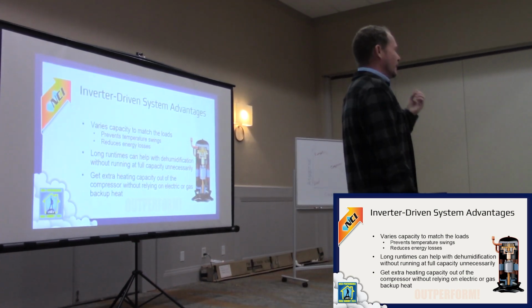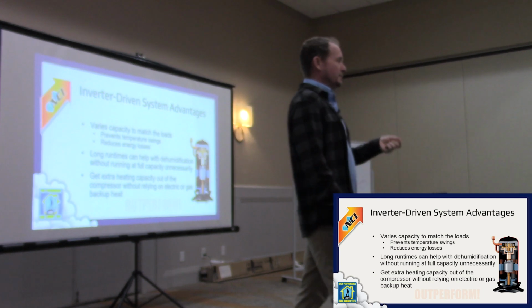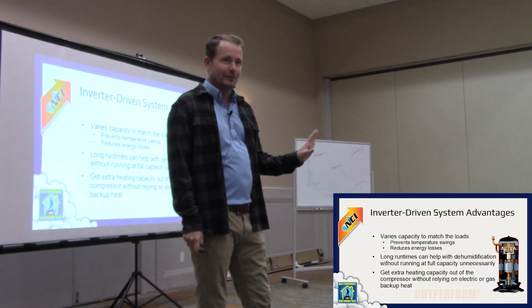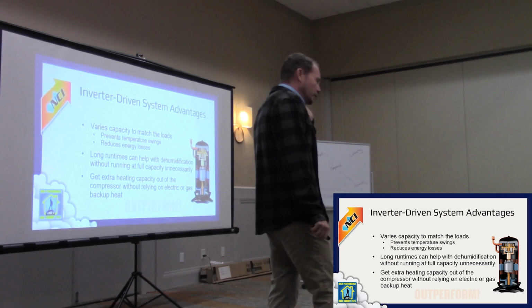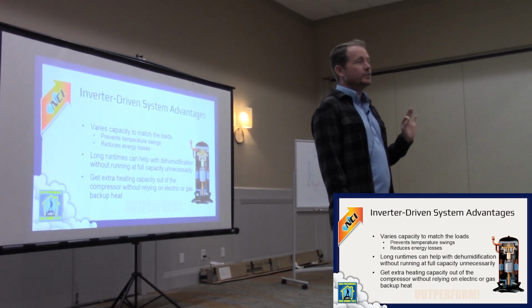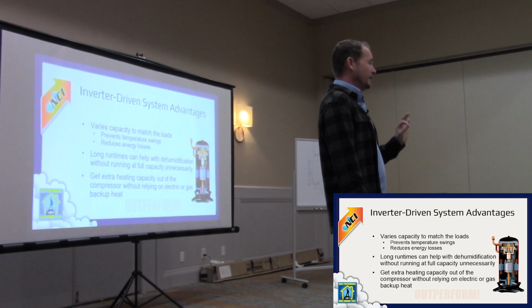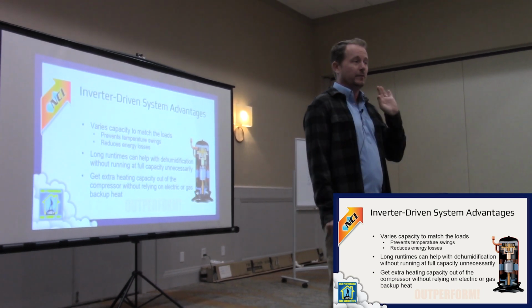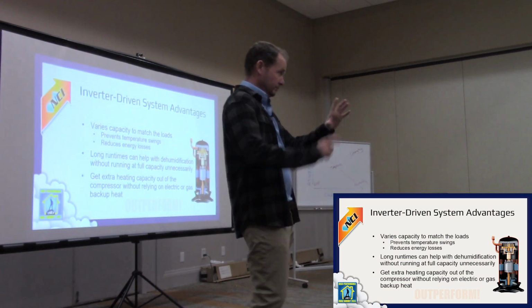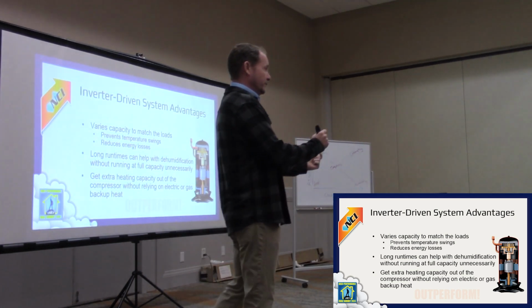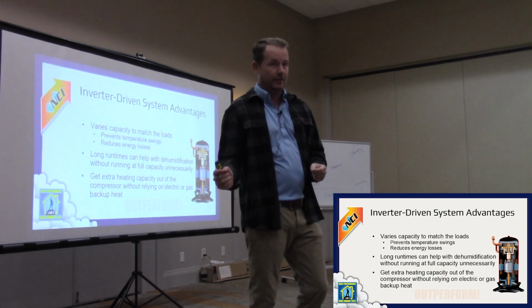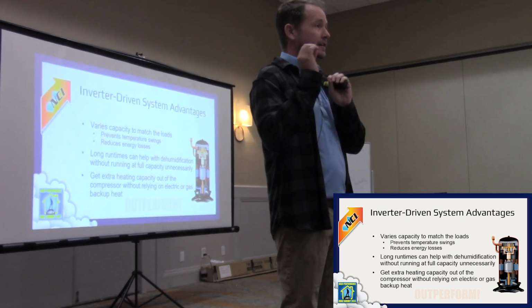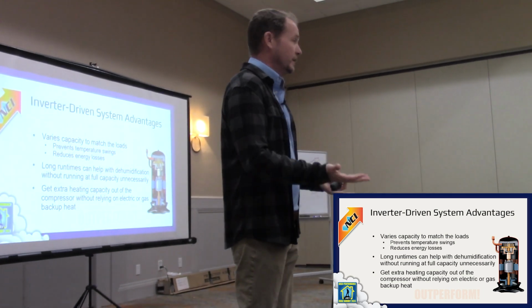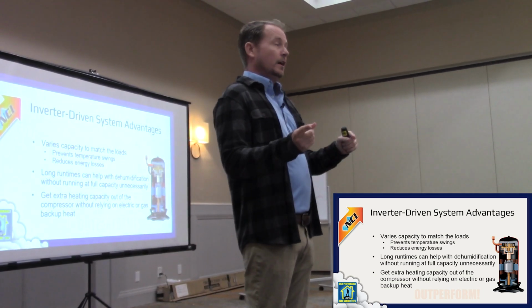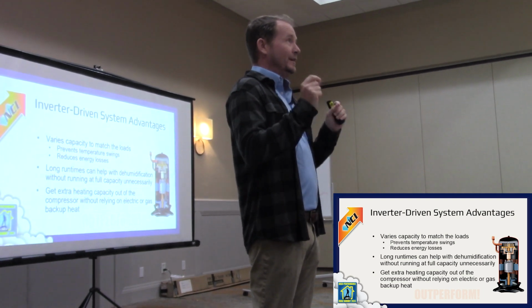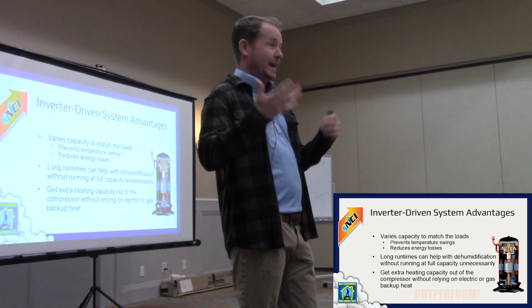The problem is that a lot of times manufacturers don't optimize for this. They optimize for compression ratio. Not going to go into compression ratio here, not too deeply. But what they're really optimizing for is energy consumption. So when you see a 30 SEER ductless system, I don't need to know anything else. I know that it's going to be terrible at dehumidifying at that 30 SEER. Because sensible BTUs are much less expensive to get out than latent BTUs. Warming an evaporator coil is a very energy efficient strategy, just like we talked about, right? When you make things colder than you need to, bad on energy. We don't want to make an evap colder than we need to unless we need to get moisture out of the space. And then we just have to, because that's part of the deal.